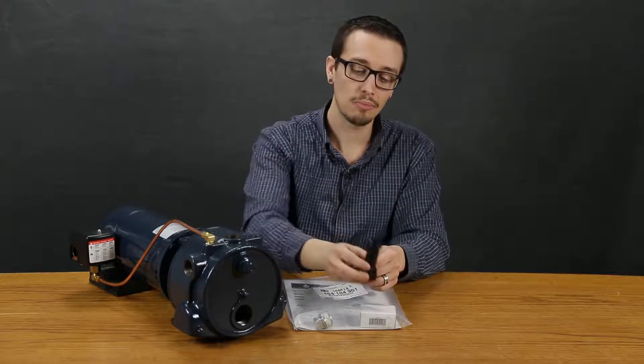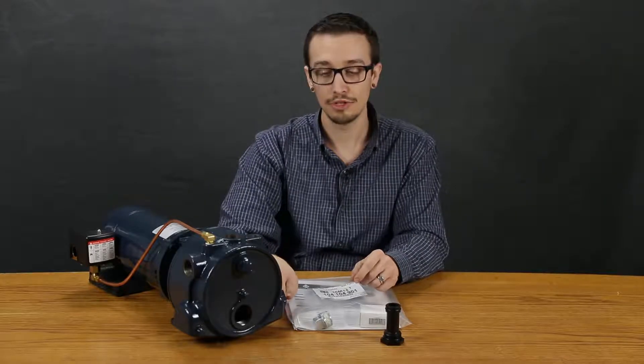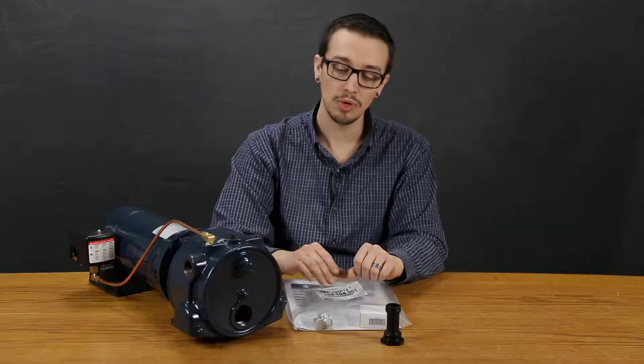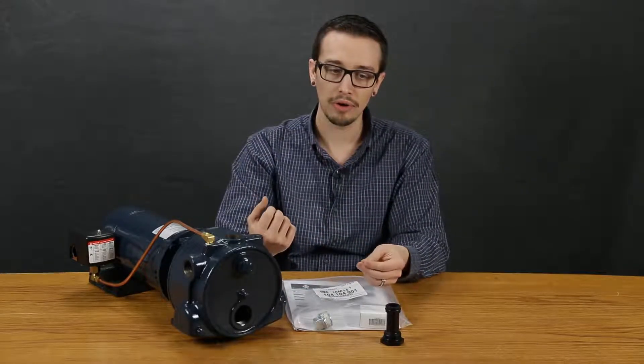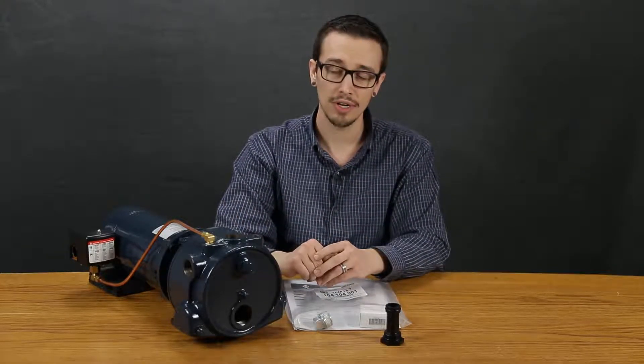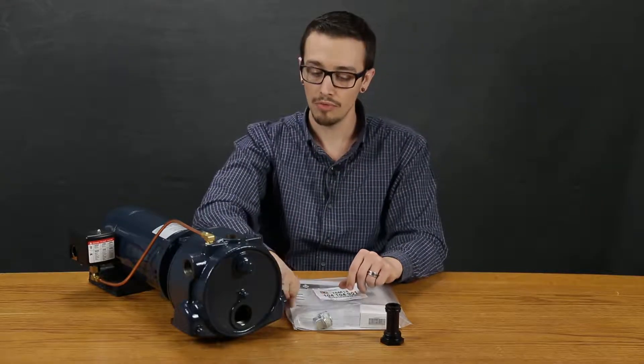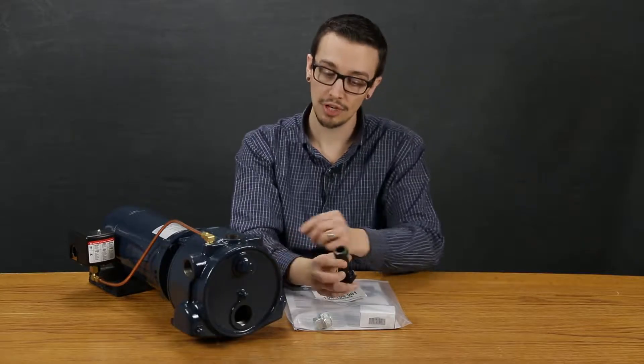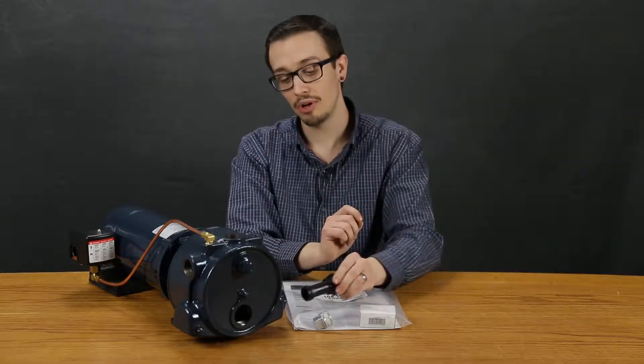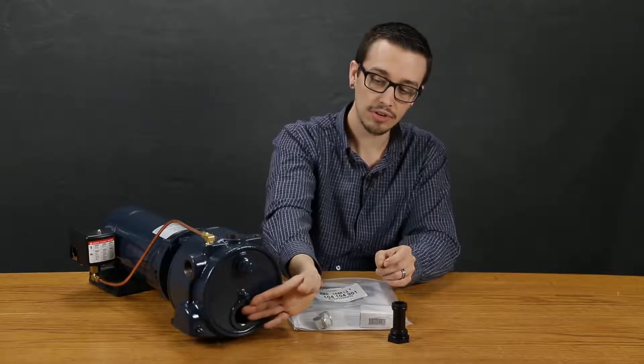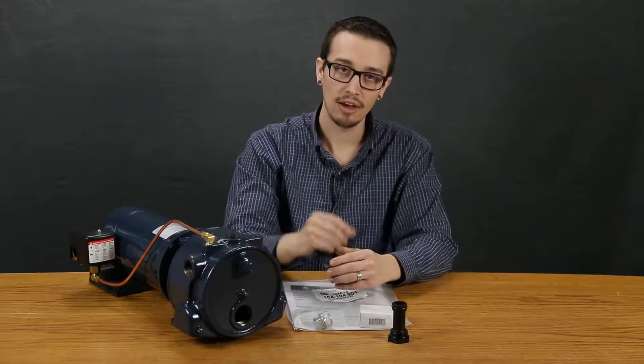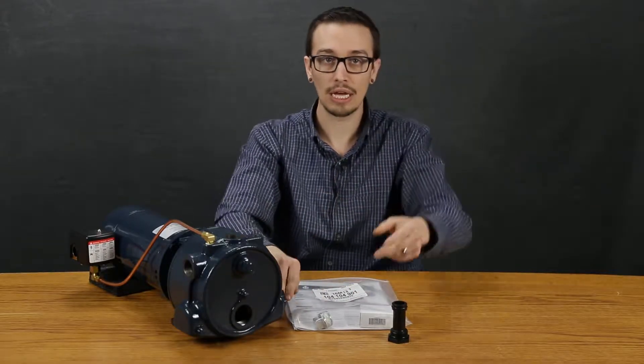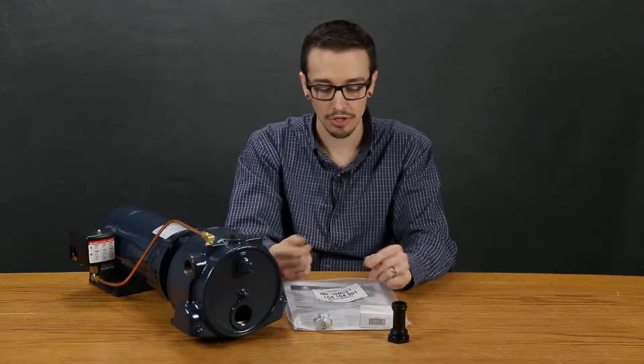This replaces the shallow well jet that's in the side of the pump here for deep well installations. If you have a deep well where your suction lift is greater than 25 feet you would remove the shallow well injector, put the bypass plug in, and then on the end of your suction line you would have a deep well injector. It just moves the injector down closer to where the suction is taking place.